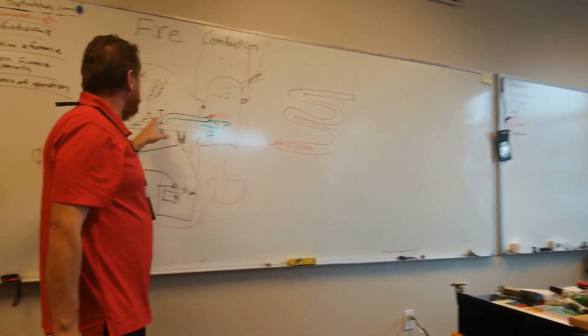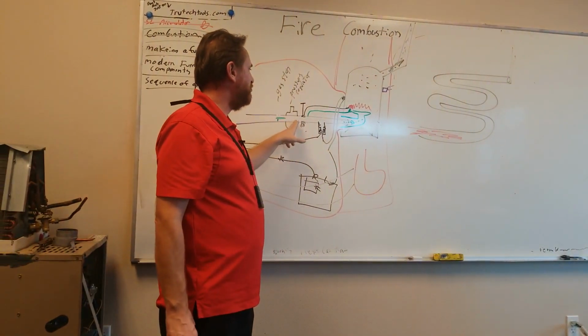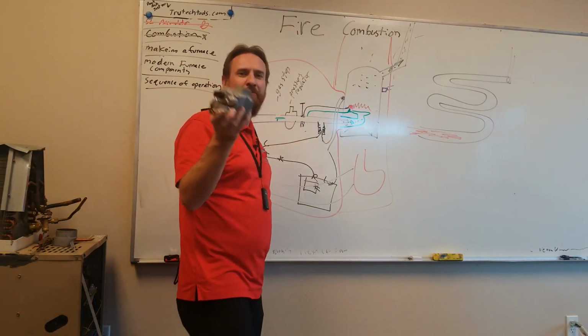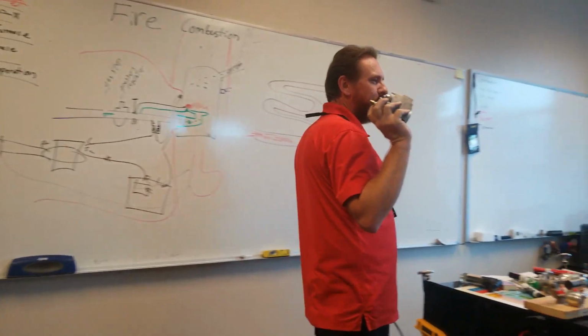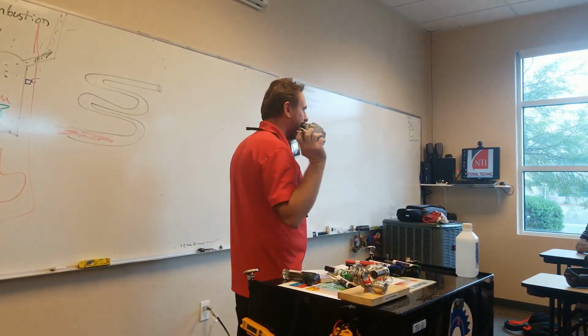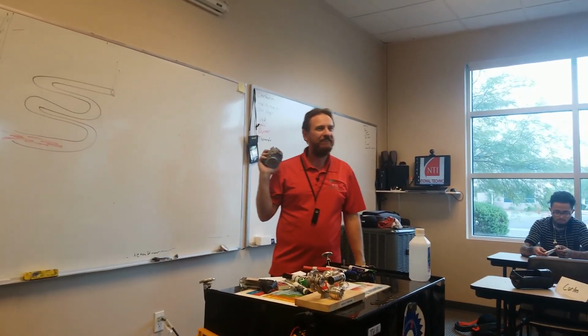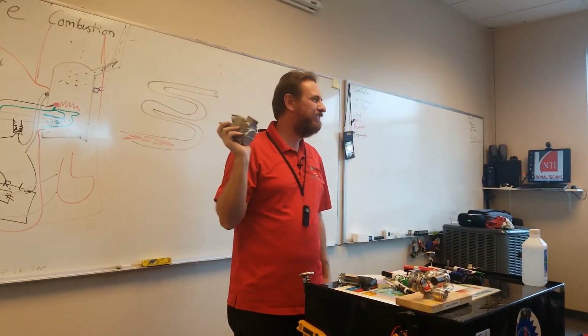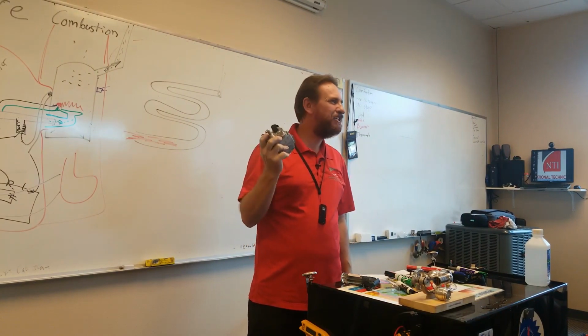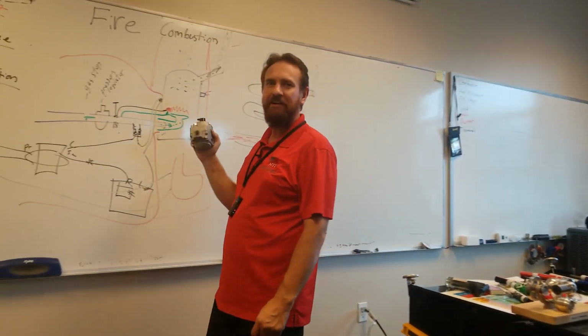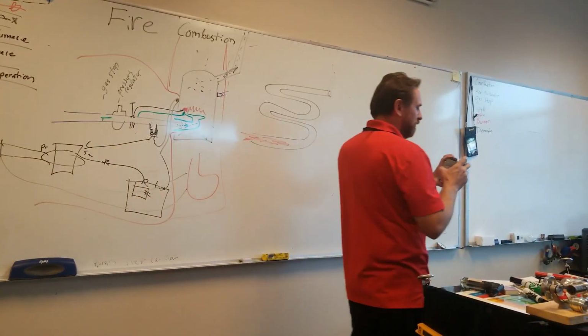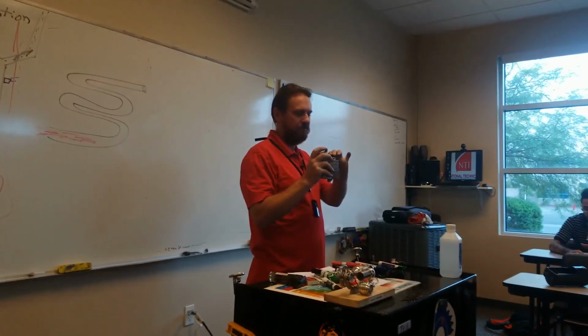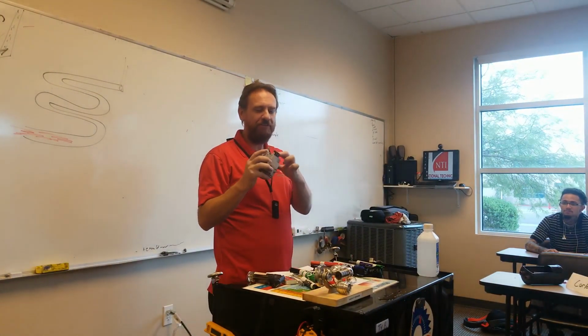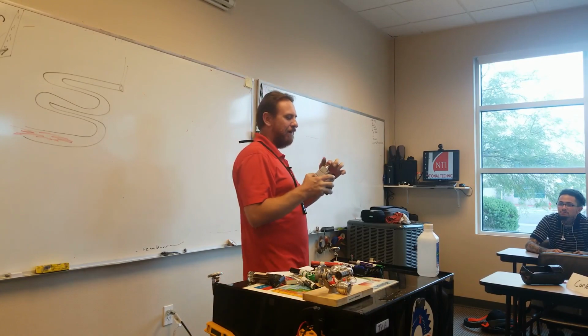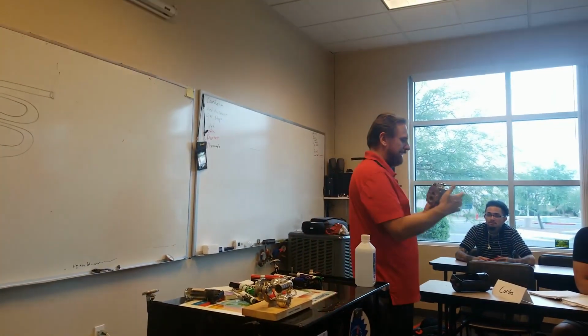Then, what we started doing also is we took all these components, the gas shutoff, the pressure regulator, the pilot valve, and the solenoid valve, and we put them into one component. Is this component a combination of multiple parts? Mm-hmm. It is. So guess what we call this? A combination gas valve. Because it's a combination of a pressure regulator, a solenoid valve, and some other stuff. So here we have the pilot, so we have to actually push it down for the pilot to work. We have 2 wires for our solenoid valve. We have an adjustment for a pressure regulator. We have a port over here for our pilot tube. And our gas in and gas out.